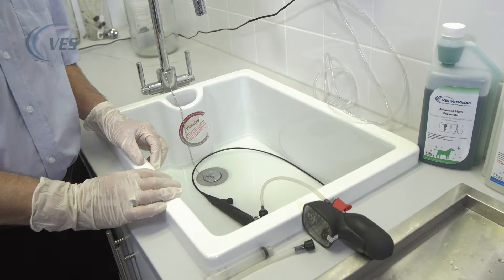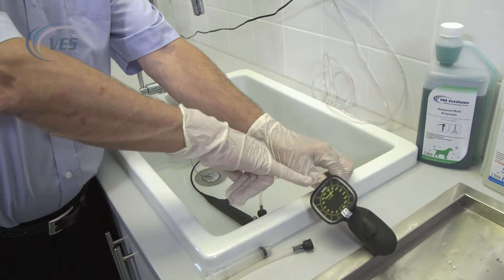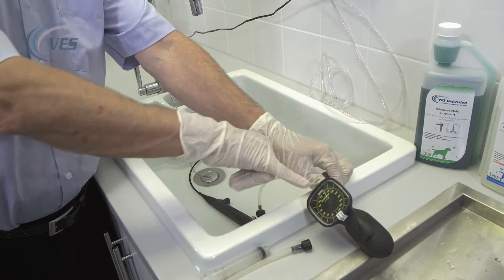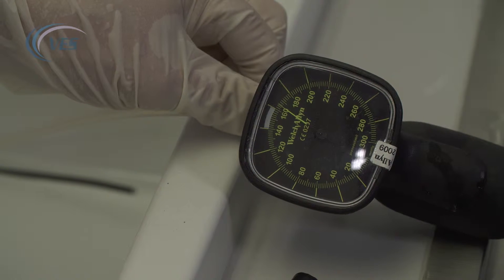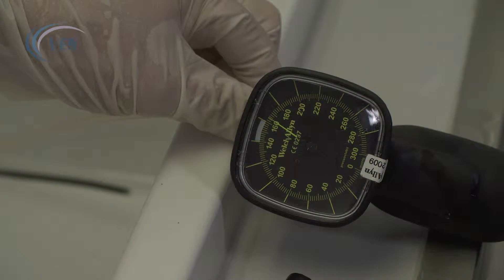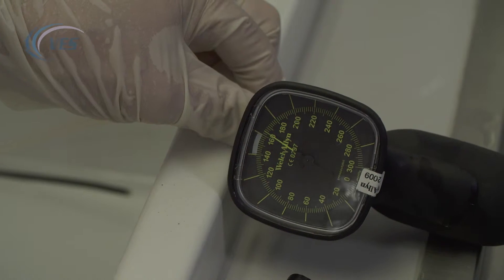With the scope immersed in the Enzymatic, we have to ensure that the leak tester remains dry, so that stays outside of the sink, and that the pointer remains constant at 160 millimeters of mercury. If that pointer starts to drop, take the scope out of the chemistry and phone our service department — it could be something that we need to talk to you about over the phone.